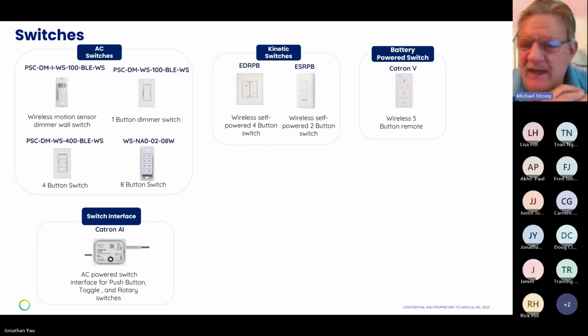The old school way of doing that was to have a relay or contactor built into the switch, with AC provided there so they could turn it on and off without going up into the ceiling. If you look at it, power comes into the room from the ground most likely, up into the wall, the gang box first, then up into the ceiling, and the first distribution box or branch circuit junction box is where our controllers go. These 4 switches that use AC power are programmable, so using AC power to power those is an easy way for us to energize our Bluetooth chipset. There are small computers inside those switches, and that's why we use AC power. Now, a low voltage version of those will be coming to a theater near you, it's just not ready yet.